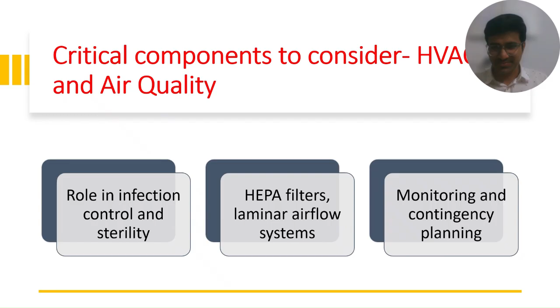Usually laminar flow systems are used in the OT, which is a unidirectional, low turbulence stream of clean air over the surgical site. There has to be continuous monitoring of pressure systems, temperature, and particle counts. You should have contingency plans for an HVAC failure, like shifting to backup OTs or delaying elective procedures. HVAC is not just about comfort and AC, it's about control. And in the OT, control means safety.